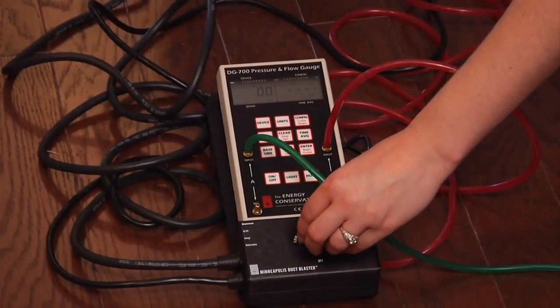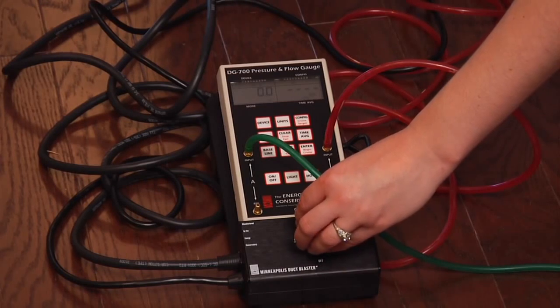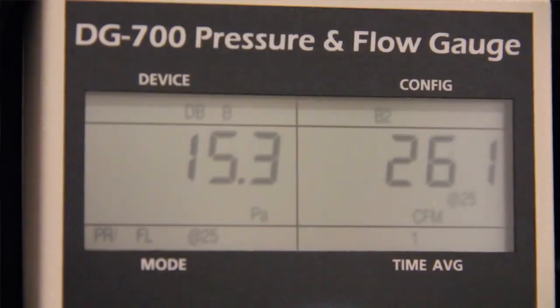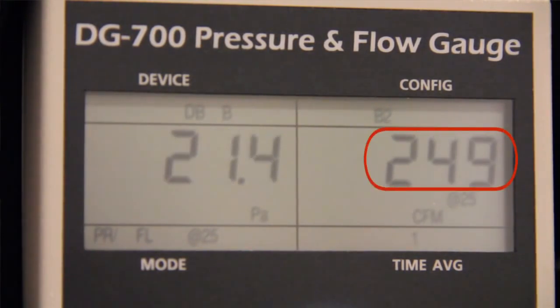To measure total leakage of the duct system, use the duct blaster to pressurize the duct system to 25 pascals, a typical pressure the duct system experiences when the air handler is operating. The right-hand side of the gauge will then display the flow required to obtain this test pressure. This will be the CFM 25.